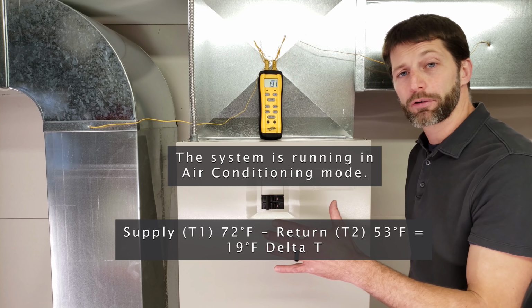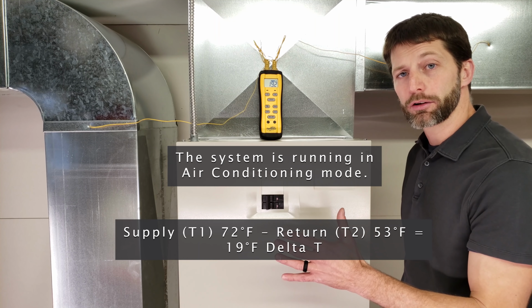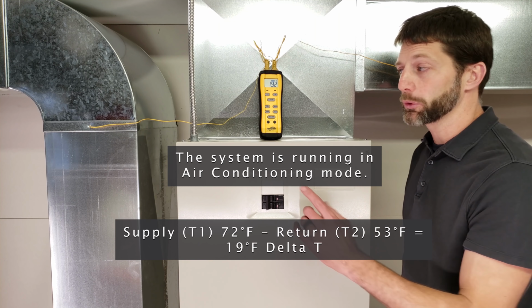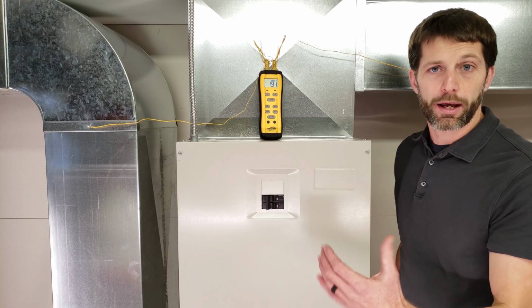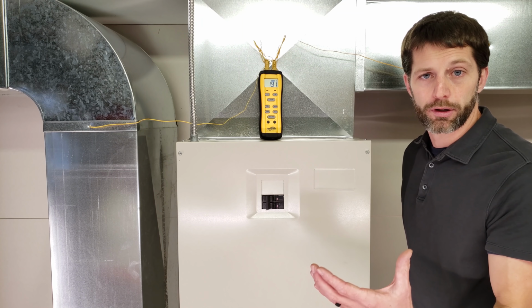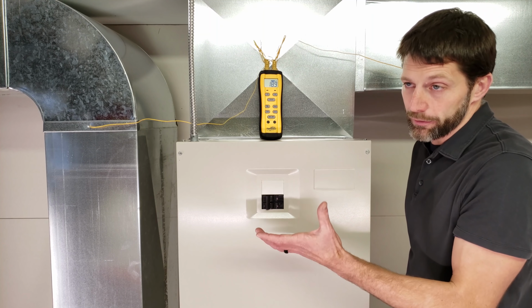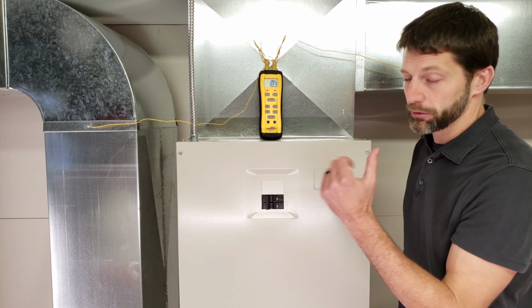So we have the system running right now, and our Delta T is roughly 19 degrees between the return and the supply. And so this system should have about 18 to 21 degrees as its Delta T because it has a TXV at its indoor coil, and the outdoor unit has good fins. It's a 16 SEER unit. So this one should have 18 to 21 degrees as long as it has good airflow.